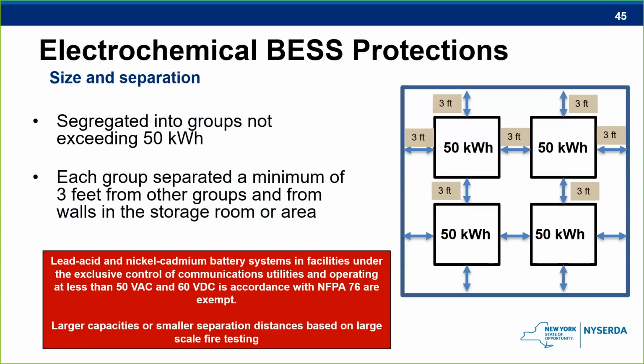And walk-in units that are near exposures, while they do need the spacing between the groups inside, they do not need spacing between a group and the wall of the walk-in unit. There are 2 exceptions to this requirement, and you'll see this on a lot of the slides coming up where we have a big red box showing where the exceptions are. So one is for communication utilities, and the other is based on that large-scale fire testing. If the test report shows that it's not a concern, you may be able to get that 3-foot distance to something less, so you can fit more.